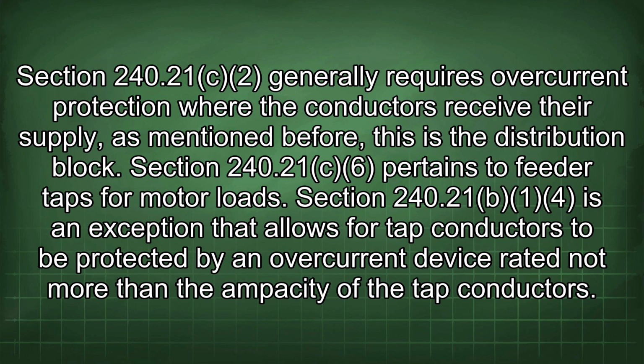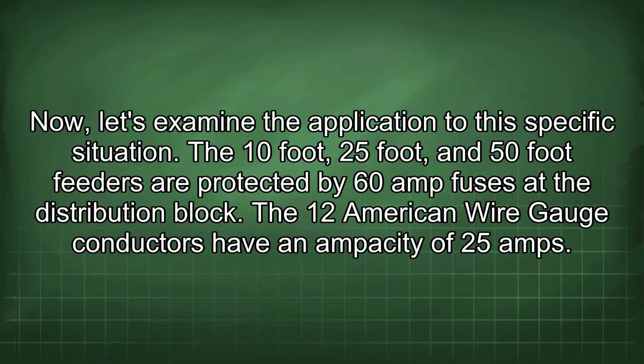240.21(b)(1)(4) is an exception that allows for tap conductors to be protected by an overcurrent device rated not more than the ampacity of the tap conductors. Now let's examine the application to the specific situation. The 10-foot, 25-foot, and 50-foot feeders are protected by 60-amp fuses at the distribution block.